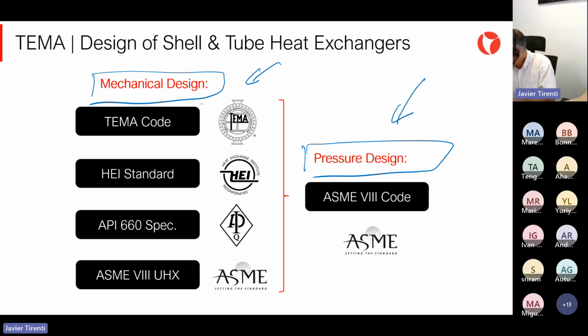Let's start with TEMA, the Tubular Exchangers Manufacturers Association. It is the most used standard for designing and specifying a shell and tube heat exchanger. We find requirements in terms of size, tolerances, and procedures to develop the overall design. But when it comes to pressure components, TEMA directs us to ASME Section 8, Division 1, 2, or 3 for pressure parts. The same happens with the HEI standard, the Heat Exchange Institute.